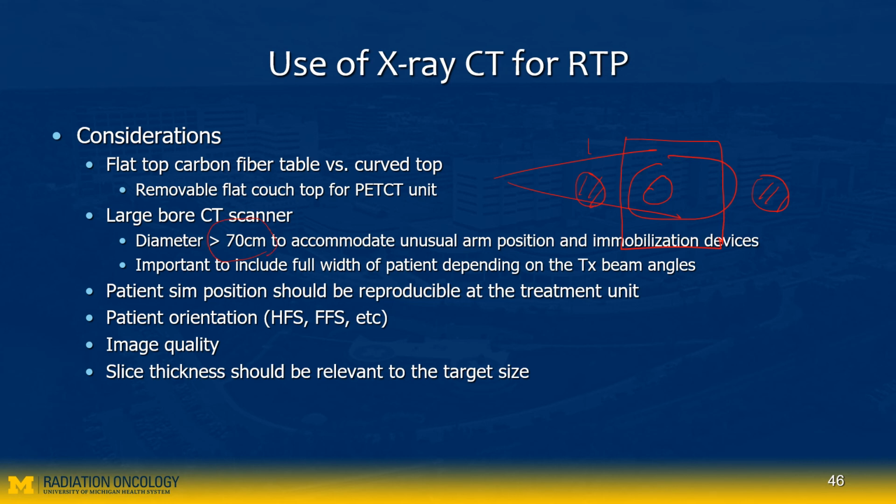What is the downside? If your CT scanner bore is big, the distance between your X-ray source and the detector has to be larger, so inherently the image quality is not as good. Image quality can be worse.